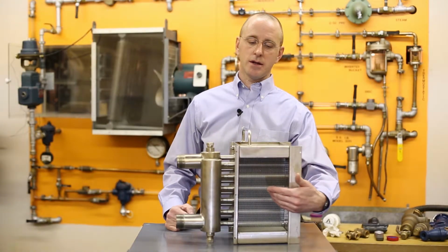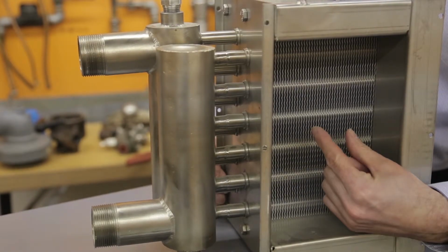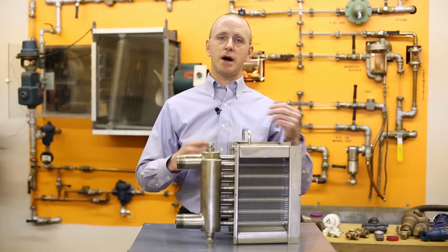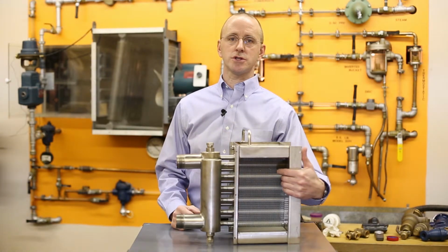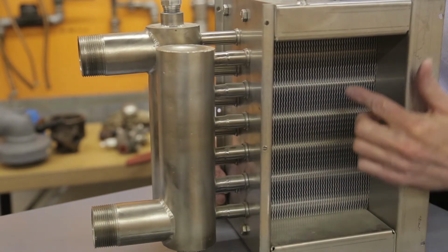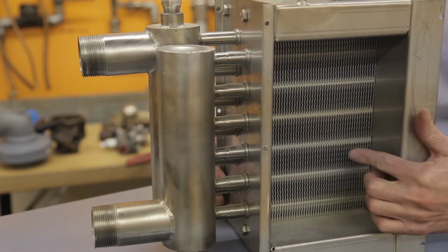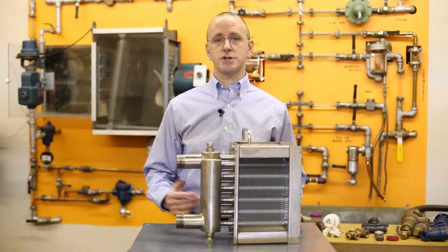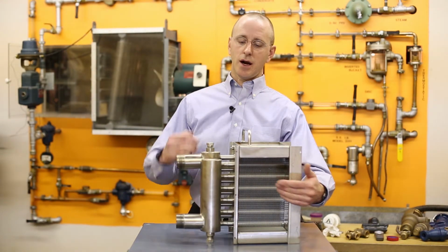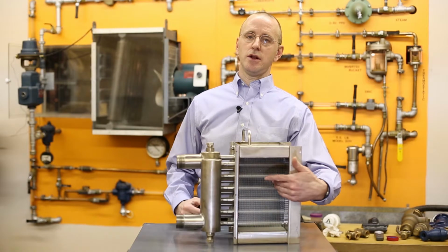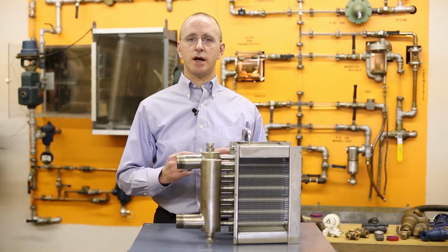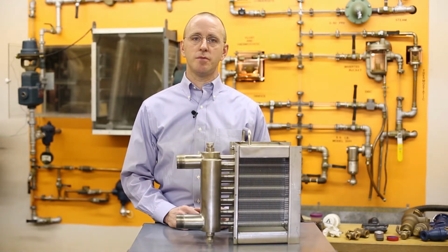Sometimes instead of an aluminum fin, you need to go to a copper fin to maintain a copper-to-copper fin tube bond to make sure you don't have differential expansion issues. Or if you've got some process conditions, some airside conditions that are corrosive, then we can go from an aluminum fin to a stainless fin or a coated fin. Or if you've got carbon steel tubes and you need to go to a carbon steel fin, again, for high temperature applications where you're concerned about that fin tube bond.